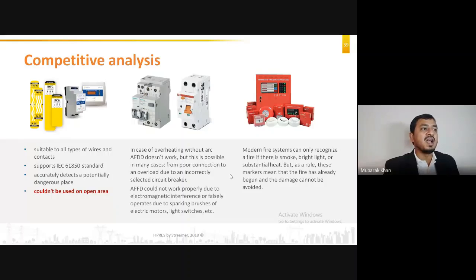Now, moreover, arc flash detection systems are of two types. One is the AFDD, which is detecting small corona type of arcs coming inside the panel. If these arcs are coming inside the panel, the waveform of the voltage changes, and these devices detect that waveform change. It is only suitable for very small loads, for 220 volt household applications, not suitable for industrial. And secondly, it is only detecting the arcs.